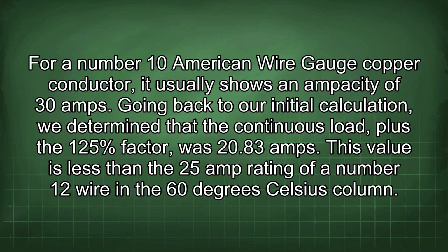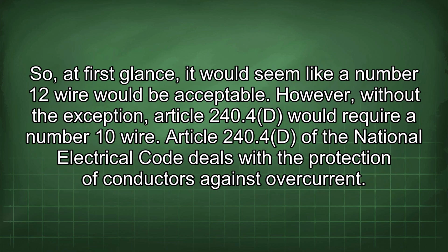Going back to our initial calculation, we determined that the continuous load, plus the 125% factor, was 20.83 amps. This value is less than the 25 amp rating of a number 12 wire in the 60 degrees Celsius column. So, at first glance, it would seem like a number 12 wire would be acceptable. However, without the exception, Article 240.4d would require a number 10 wire.